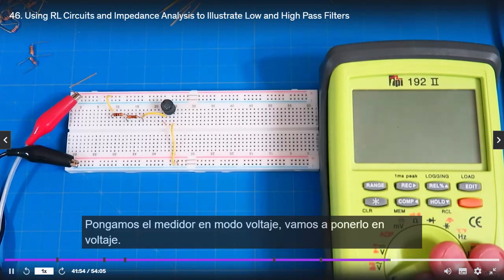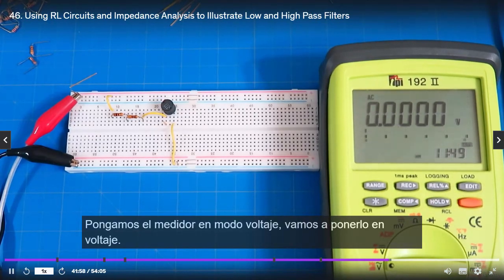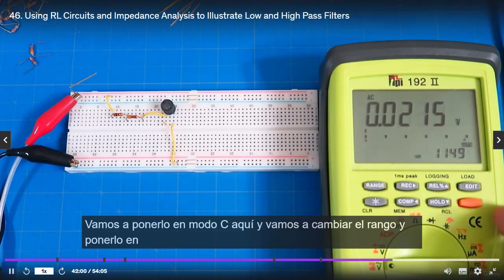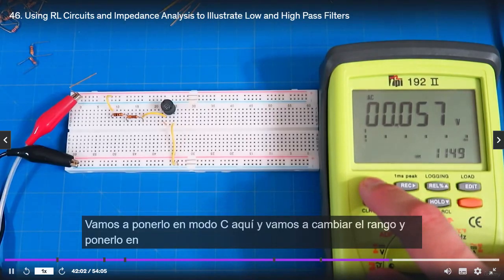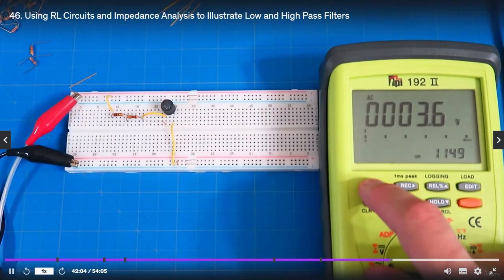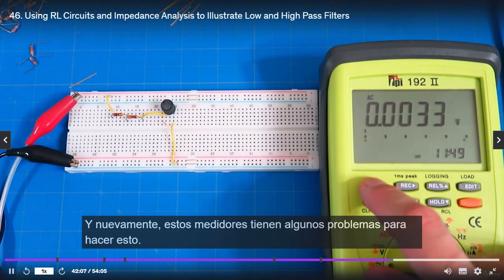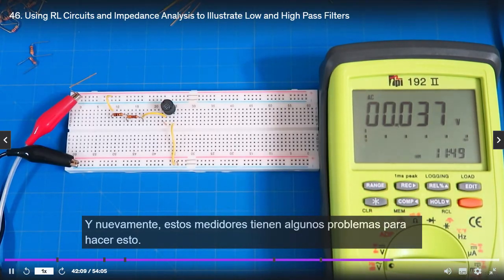So let's put the meter into voltage mode. We're going to put it in AC mode here, and we're going to change the range and kind of put it in the middle. And again, these meters have a little bit of trouble doing this.